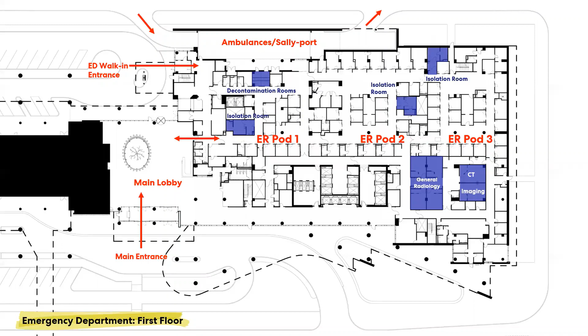Decontamination rooms are located between the ambulance bay and the emergency department. Each of the 3 20-bed pods has one isolation room with negative pressure. Negative pressure prevents air within the room from flowing out and into the corridor. All air within the room is exhausted out of the building and not recirculated. To provide even greater flexibility, entire pods, even all the pods, can be converted to negative pressure to prevent the spread of an airborne contagion. To the southeast of the pods are imaging rooms and the emergency department support spaces.